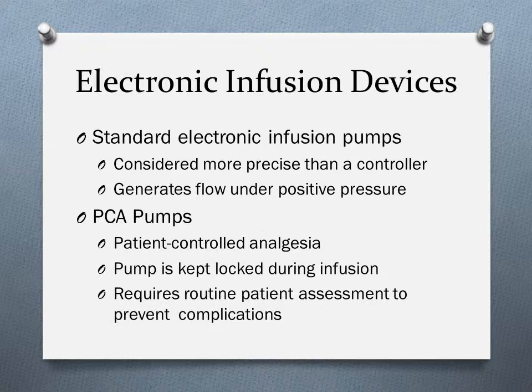It will run at a KVO rate when the infusion is complete, of 1 to 4 mLs per hour, and the displays will vary depending on the manufacturer. It may show volume infused, the dose delivered, a KVO rate, volume detector, occlusion, malfunction, low battery, may show you that the door is open or the infusion is complete, in addition to other things. It is available in a multi-channel design for multiple fluid and drug administration.